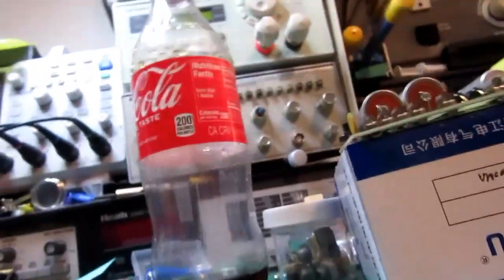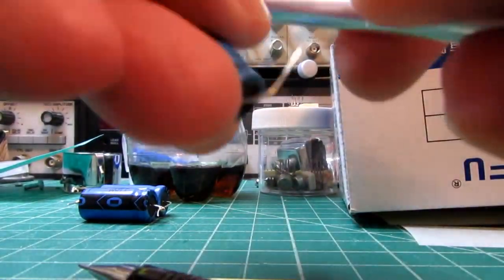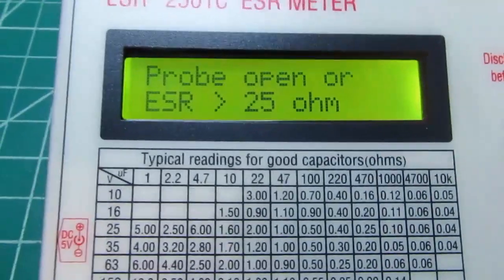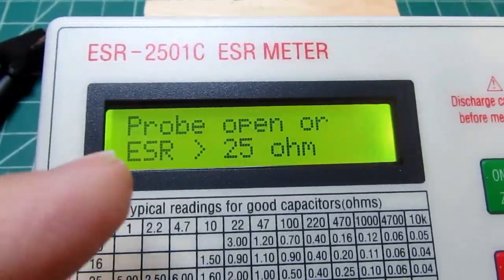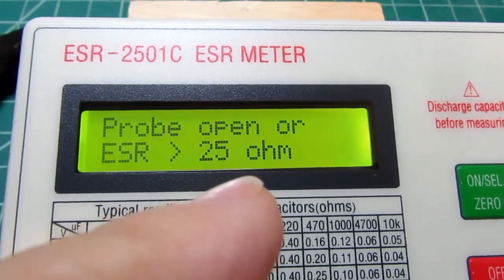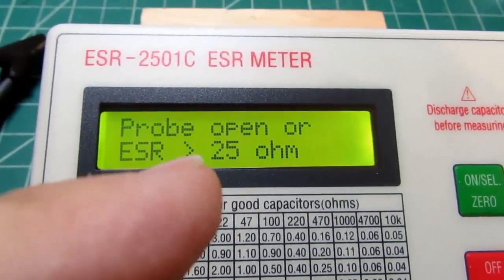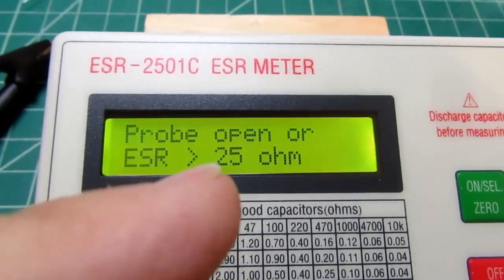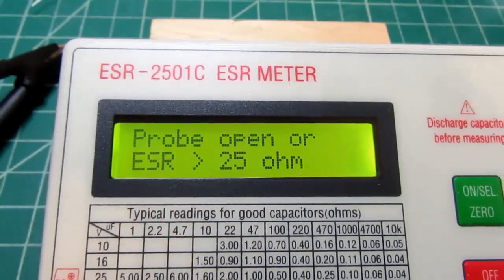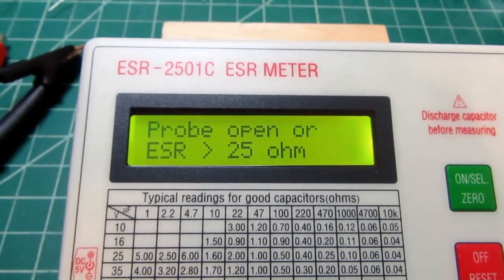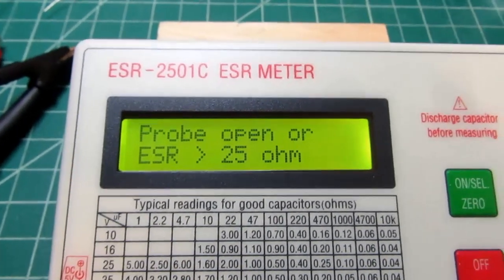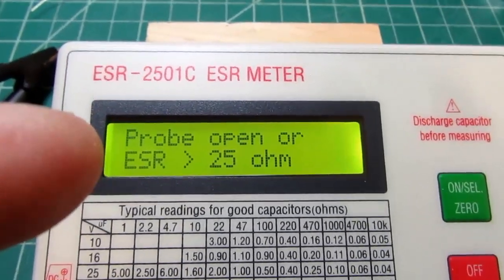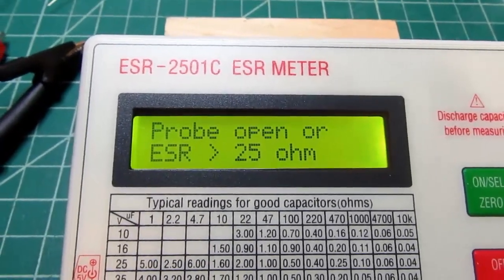I'm going to go up to the 470 microfarad cap. First I'm going to short its leads out. Notice that when there's nothing connected to the test leads, the ESR is shown as greater than 25 ohms, or probe open. It does not register any resistance in any mode greater than 25 ohms, it only goes up to 25 ohms. So if you see that in ESR mode, you know something is wrong, you're not getting a valid reading. So let me reconnect this capacitor.